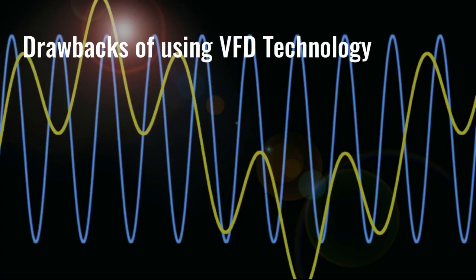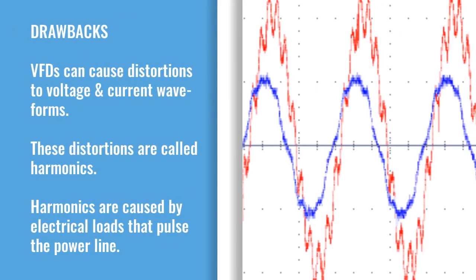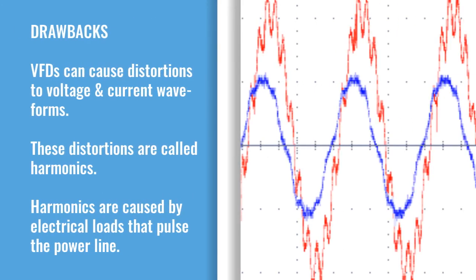Now let's talk about some of the drawbacks of using VFD technology. VFDs can cause distortion to voltage and current waveforms. These distortions are called harmonics, and they are caused by electrical loads that pulse the power line.